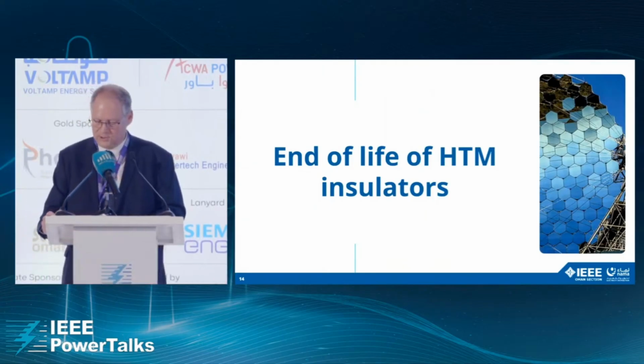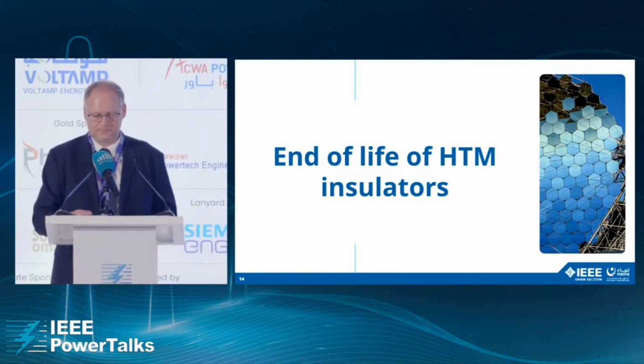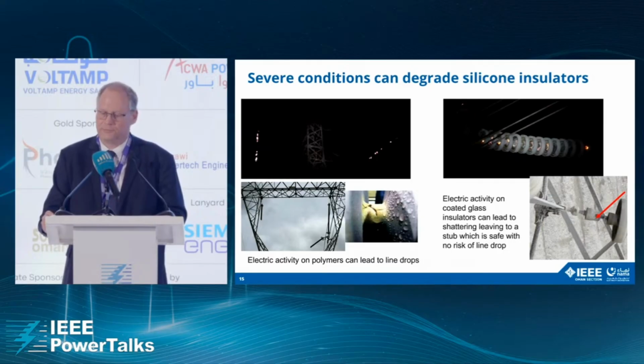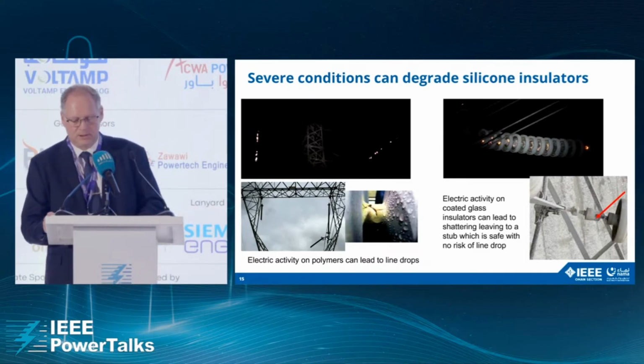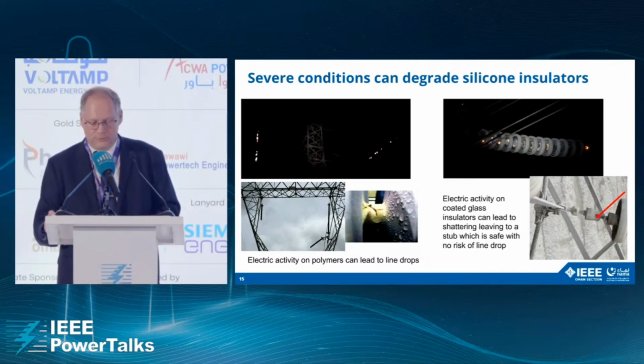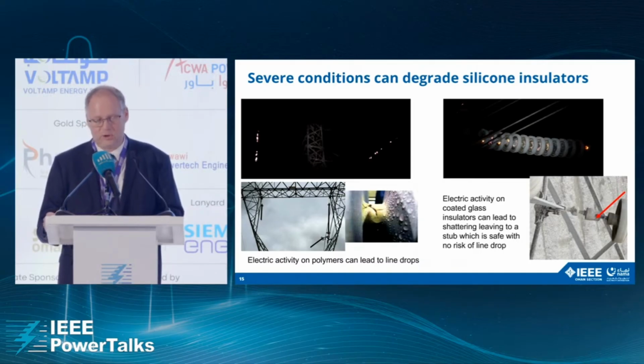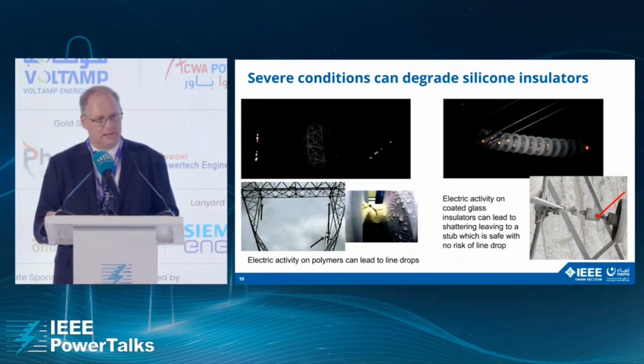An important parameter to consider is the estimation of the end of life of these coatings. In service, silicone insulators may suffer from significant degradation over time when they are exposed to severe environmental conditions. Corona effect, and in particular the water drop-induced corona effect, is the most harmful phenomenon for composite insulators, which can result in a complete line drop when the degradation reaches the fiber core of the insulator, as you can see on the bottom left. For silicone-coated insulators, the electrical activity can cause cracking and erosion of the coating, creating hot spots locally on the surface. And when this erosion reaches the glass surface, the heat induced can lead to what we call the shattering of the glass disc. However, the remaining insulator that we call a stub is safe and keeps sufficient mechanical strength to avoid the line drop.